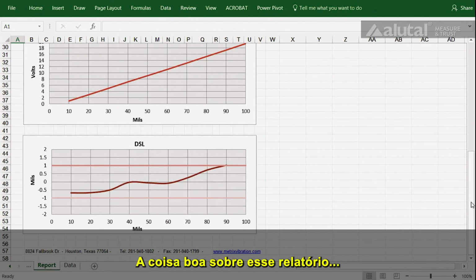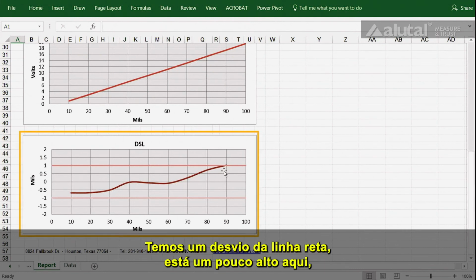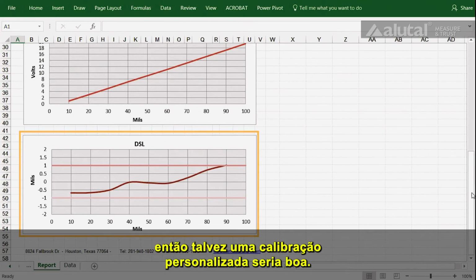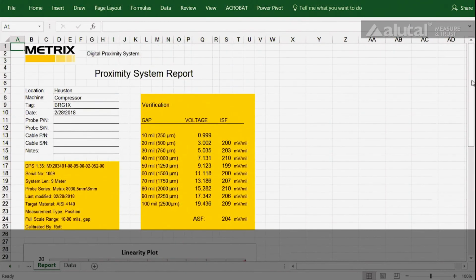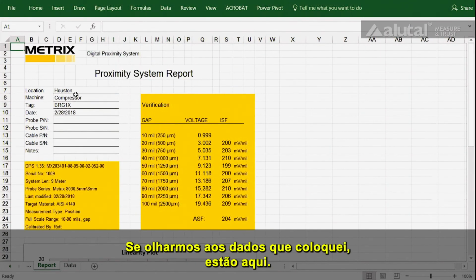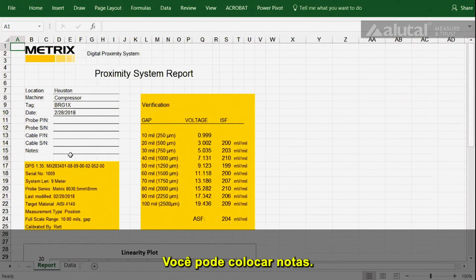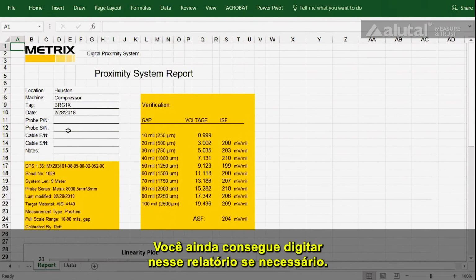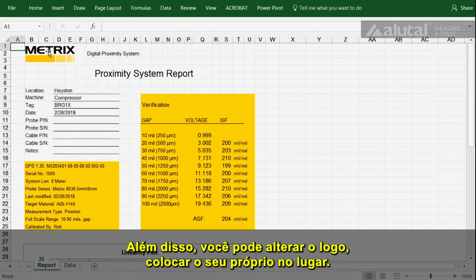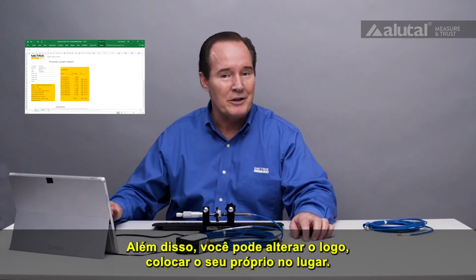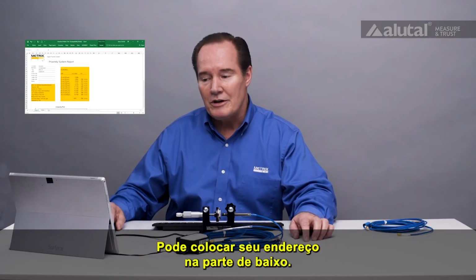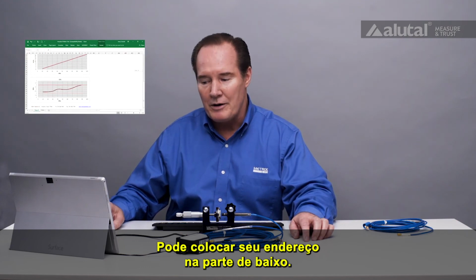The nice thing about this report, deviation from straight line, a little bit high here, so maybe a custom cal would have been in order. If we take a look at the data I put in, it's here. You can put notes in. And you can still type into this report if I needed to. I can amend this report here. So it gives you a lot of flexibility. Also, the logo you can change out. You can put your own logo in. You can put your address information down at the bottom.